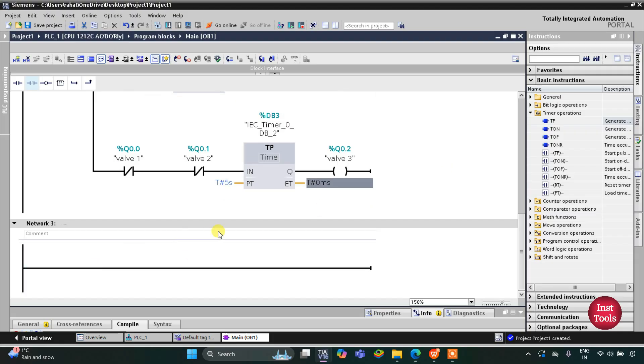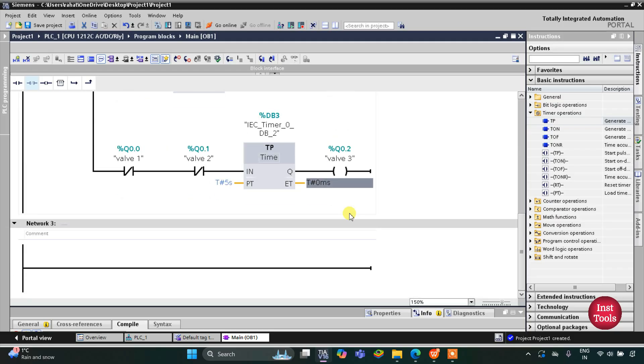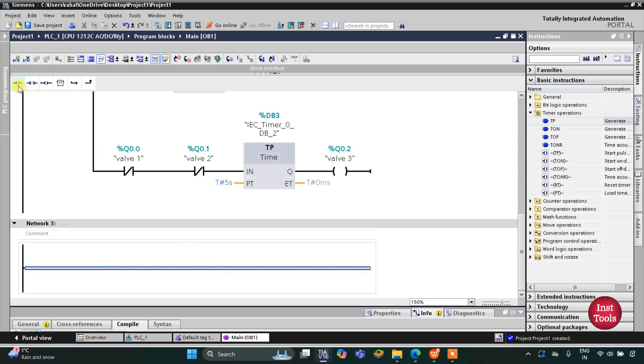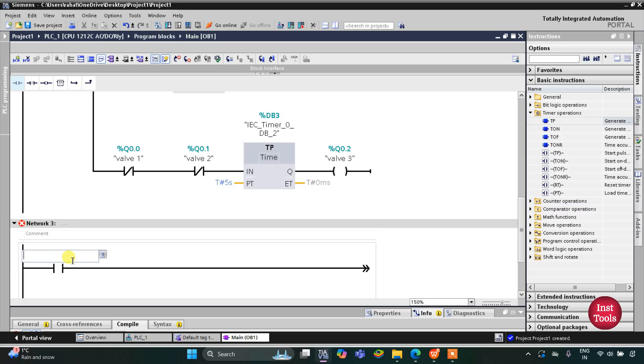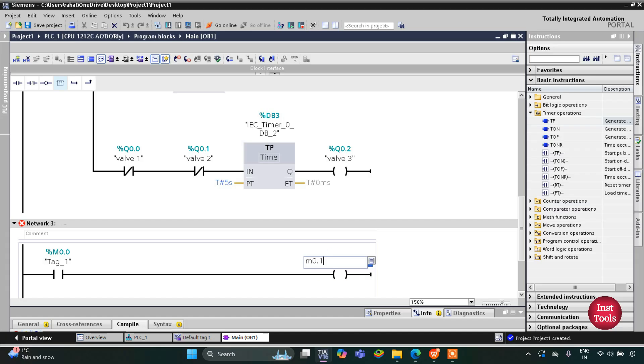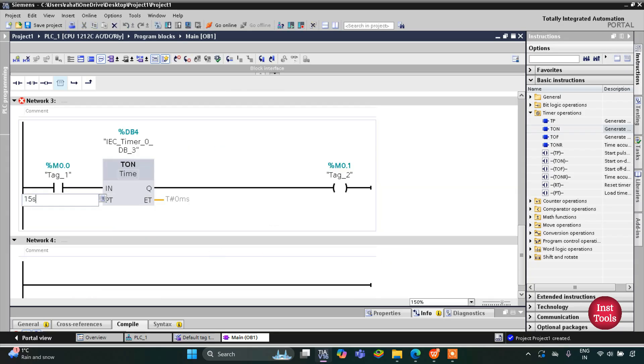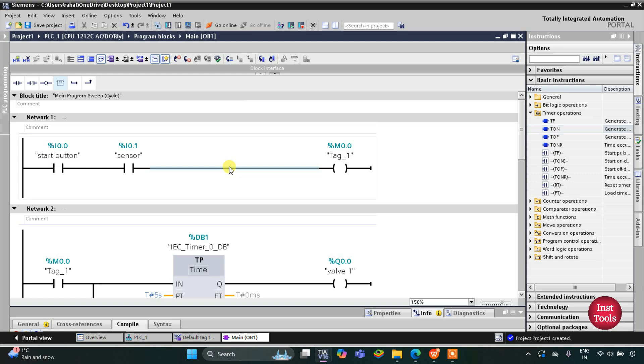Valve 1 operates for five seconds, Valve 2 for five seconds, and Valve 3 for five seconds, totalling 15 seconds when the valves are open. I insert a normally open contact M0.0, which will turn on memory bit M0.1 after 15 seconds — the preset value for this timer is 15 seconds. M0.1 is then used as a normally closed contact, which puts the system in a loop.